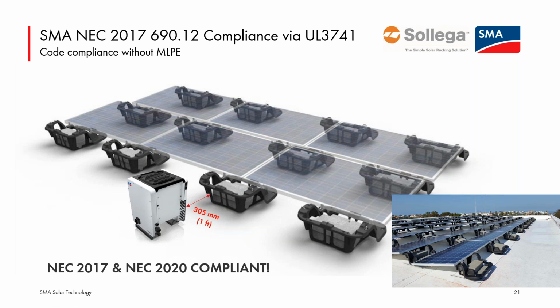Again, the CORE1 can be used with those AP Smart devices if that is desired. If the CORE1 can be placed close to this Sollega or Iron Ridge racking system, and again, per code, the array includes all the support structures, so that includes all of these ballast tubs here, then that's an additional way to comply with the latest rapid shutdown requirements. But if the designers do not see a need for DC optimizers at each system, and the module level devices are there simply for code compliance, maybe it makes sense to go via this UL 3741 listing to achieve all of the requirements of 2017 or 2020 NEC.